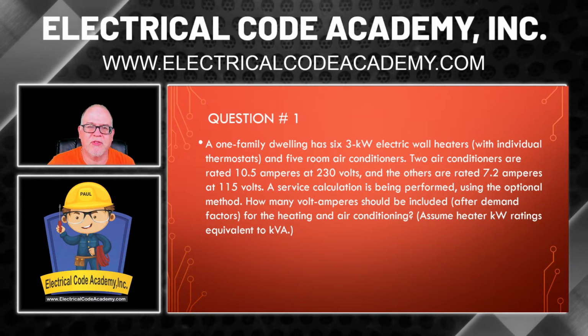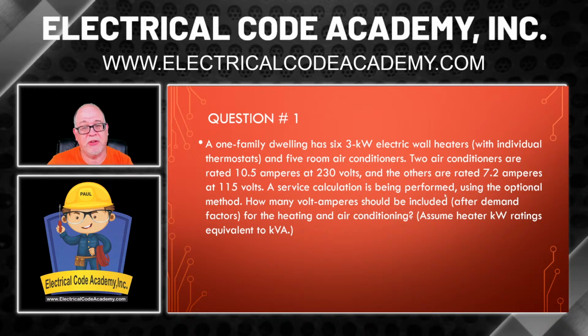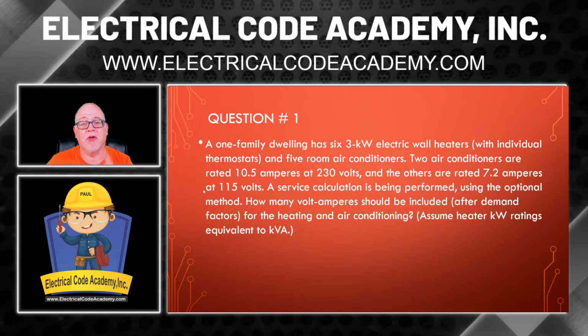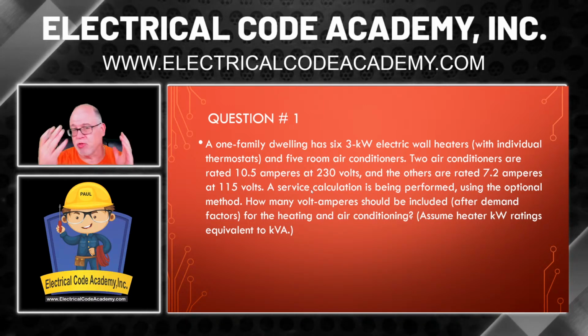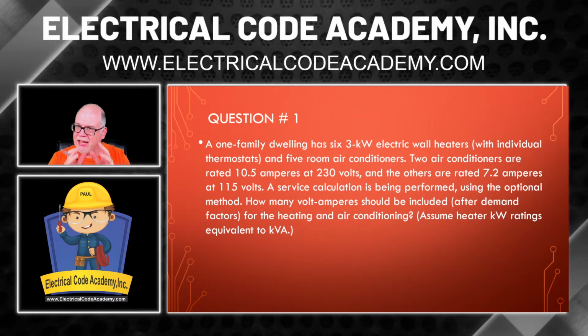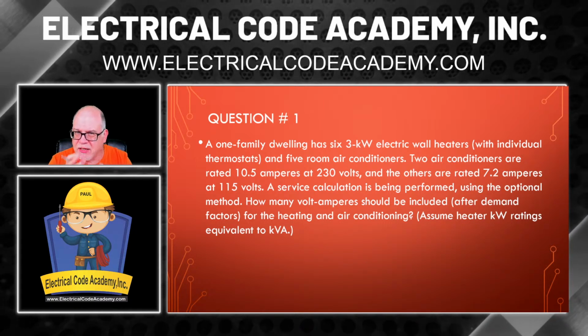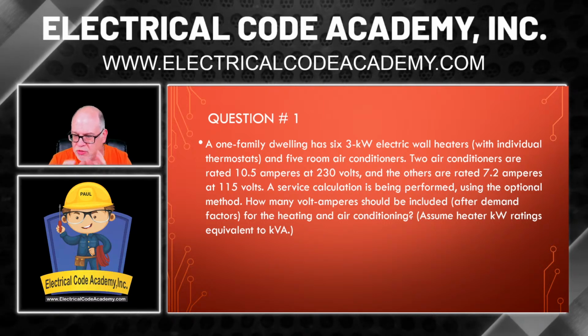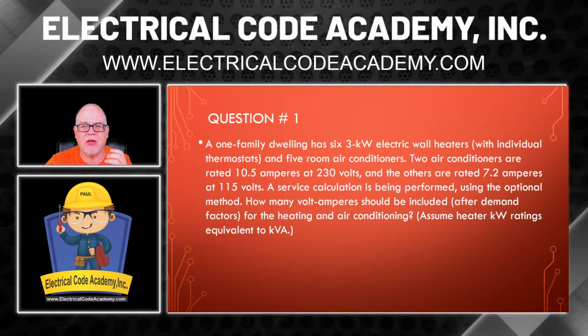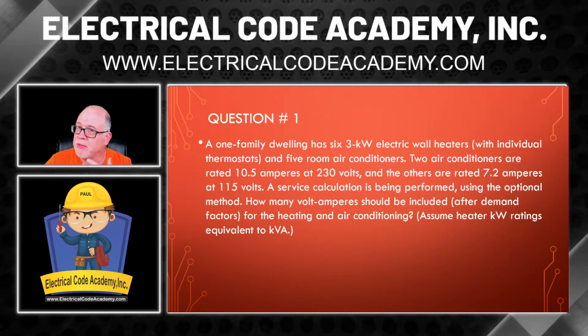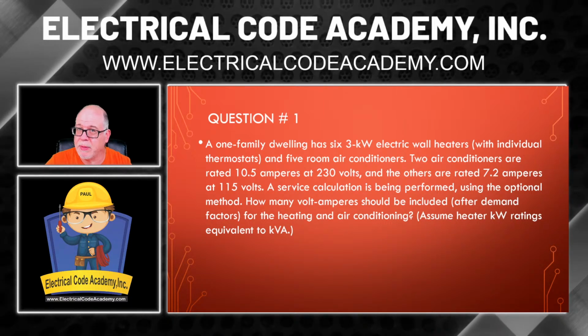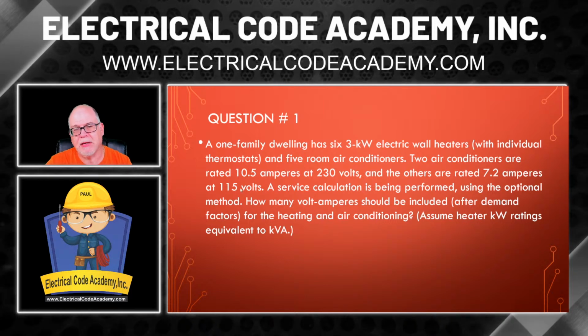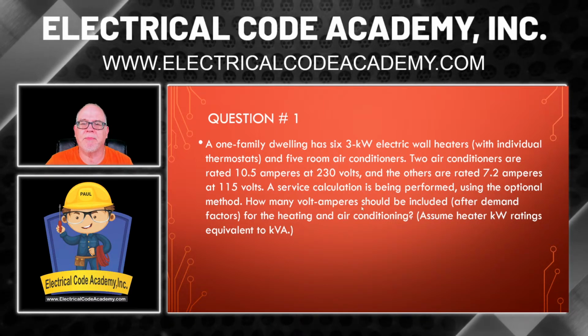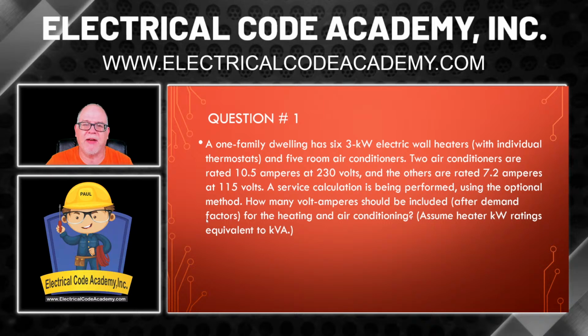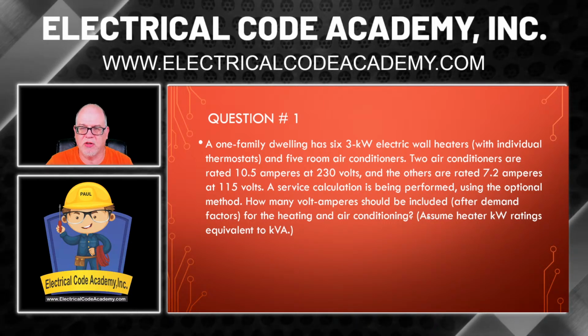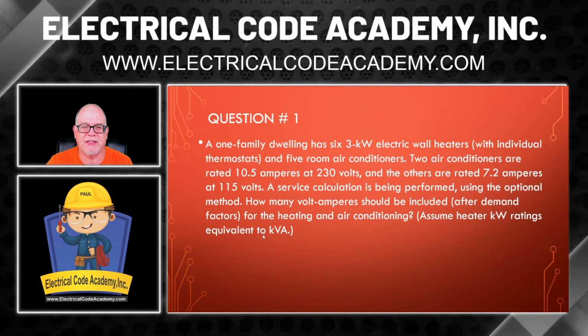All right, now it goes on to say, a service calculation is being performed using the optional method. So they'll be using the optional method to do their overall service calc. But it seems like we're only being asked to do the AC and the heat and compare the two. That's all we're being asked to look at right now. But it is reminding you that they're using the optional method, so that's going to put you in the optional area. That would be part 4 of 220, right? Okay. It says, now, how many volt amperes should be included after demand factors for the heating and air conditioning? Assume heater kW ratings are equivalent to kVA.